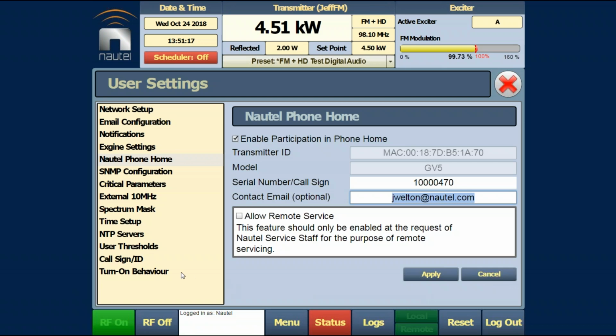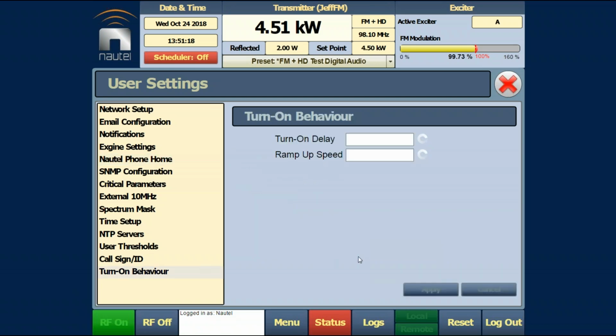Jeff, I know you wanted to look at turn-on behavior as well. I don't know if this is unique to us, but I know one of our big competitors doesn't do this. If you're connected to a generator, you have the ability to delay how long the transmitter turns on. Your generator controller may take care of that for you, in which case you could leave it at 0. But the other really cool thing is we can slow down the ramp-up speed, how fast the transmitter ramps up to full power, so we can lengthen the time it takes for the load to be applied to the generator.